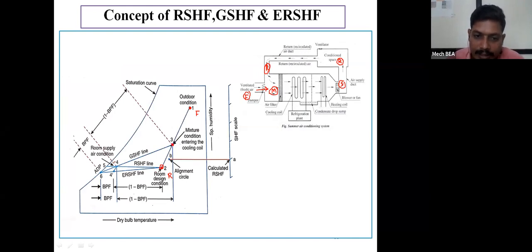Point number 3 is indicating the condition of mixed air. It is the condition of mixed air entering the cooling coil or heating coil. After passing that mixed air over this cooling or heating coil, I get the condition of supply air. So this point number 4 is indicating the condition of supply air.